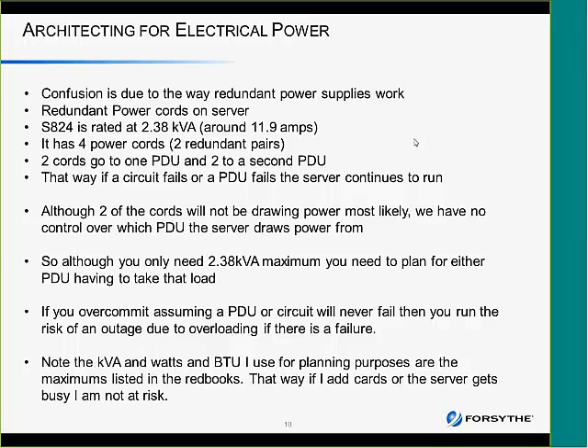The reason for that is, let's say we're currently using PDU 1 and we're pulling our 2.38 kVA. The circuit fails, or the PDU fails, or the power supply fails. Now suddenly we flip over to the second PDU. Well, if you architected that second PDU so that it was full and it was just a failover for this one, then you've got a serious problem, because now that PDU is going to fail because you've overloaded it. Or you could cause a circuit breaker to go, or other things could happen.